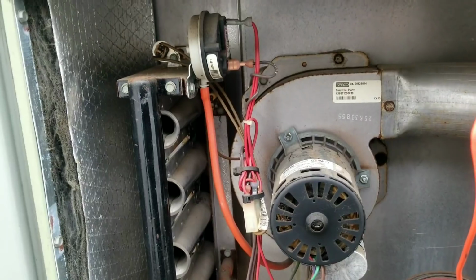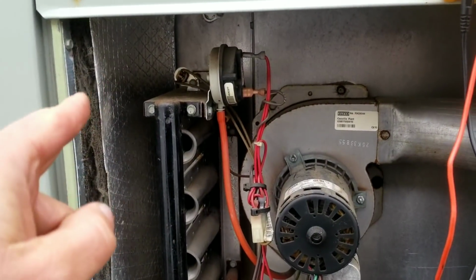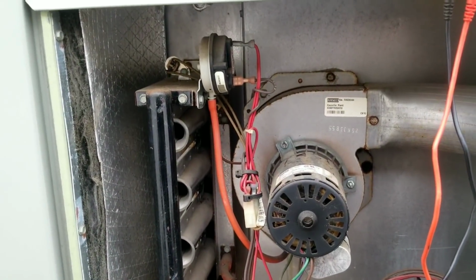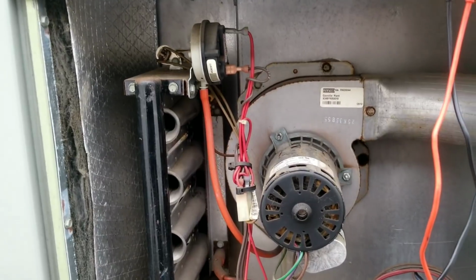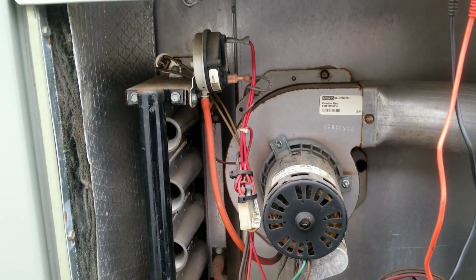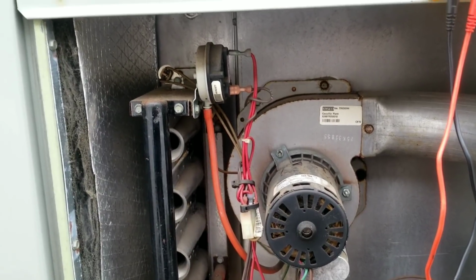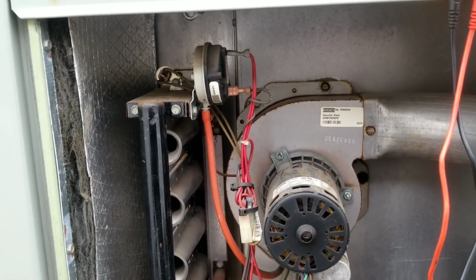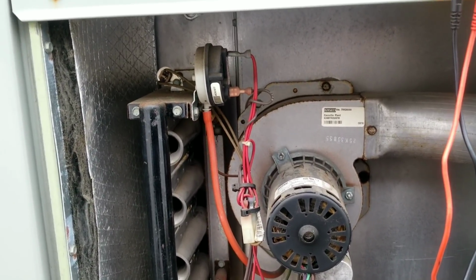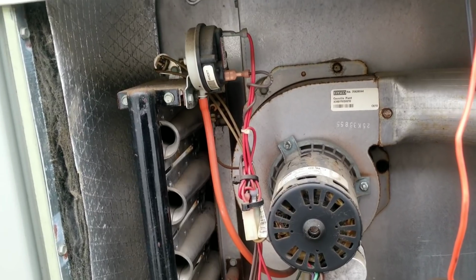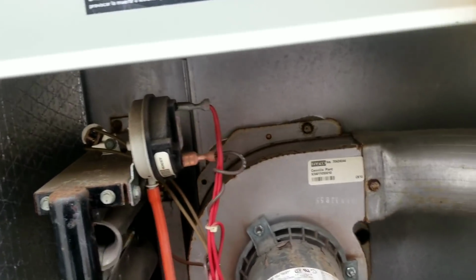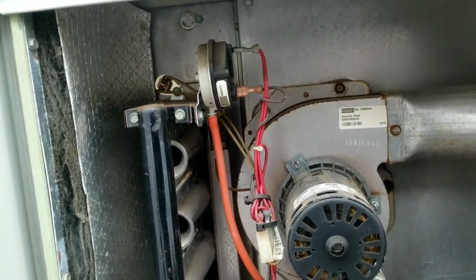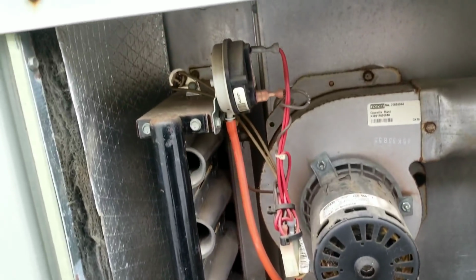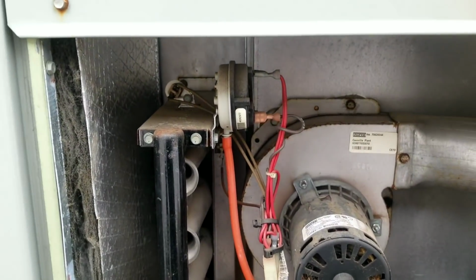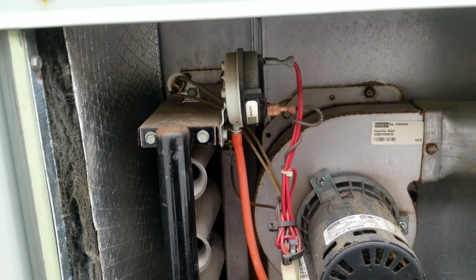What I assume happened, since our rollout switch was tripped, I'll bet that it was in heat mode and all of a sudden our inducer just died. And maybe our pressure switch didn't cut out the valve, didn't shut the valve off instantaneously, or maybe the inducer was just moving slow enough to the point where some of the flames started coming back. But I'm not 100% sure on that. I'm going to recommend they do replace that heat exchanger anyway, just based on its looks. No visible cracks, nothing I can prove, but you know.